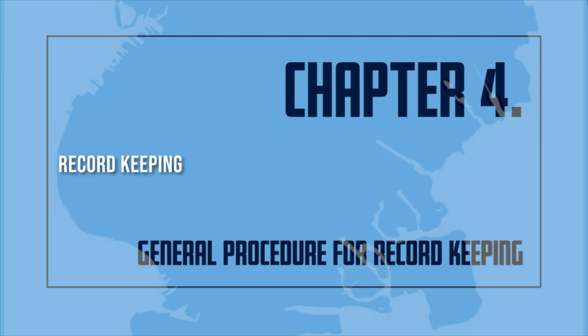A detailed inspection report shall include information relative to conditions of water supply, gravity and pressure tanks and levels therein, valves, risers, piping, sprinkler heads, fire department connections, alarms, fire, booster, and special service pumps, obstructions, and conditions of all other system equipment and appurtenances. All defects and/or impairments shall be noted on the report. Records shall be readily available to any representative of the fire department. These records are to be maintained on site by the building owner for 3 years.